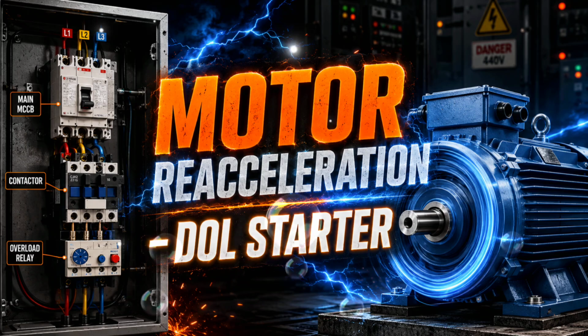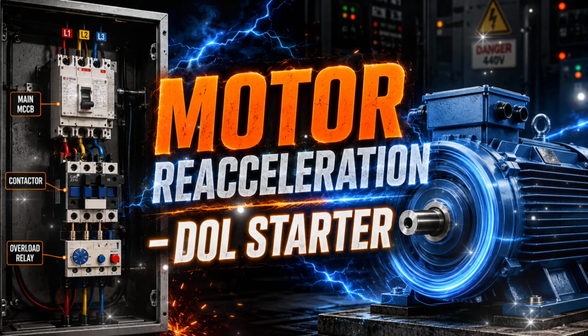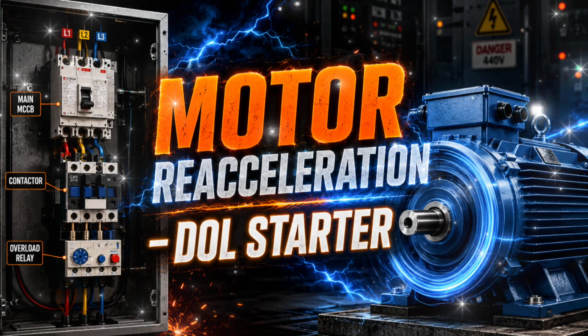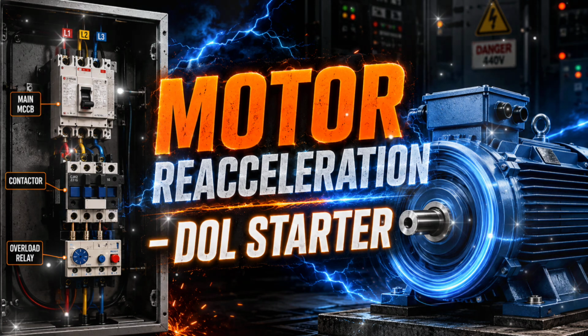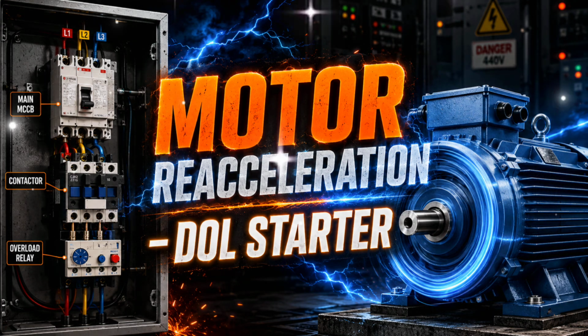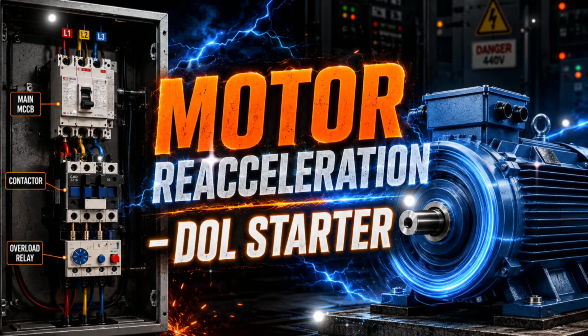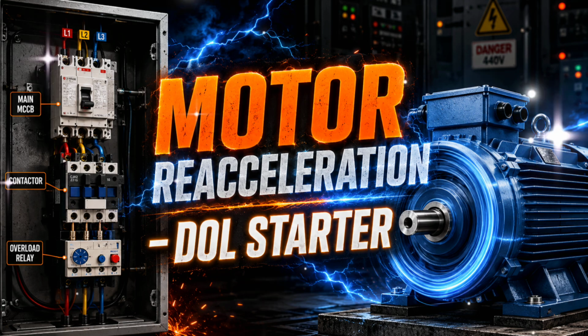Here we see a standard direct online or DOL starter panel. It consists of the main MCCB for short circuit protection, the KM1 contactor for switching, and the thermal overload relay to protect the motor from overcurrent.